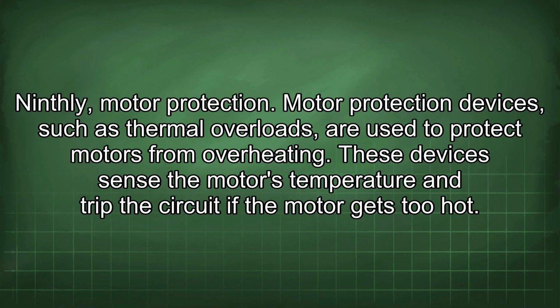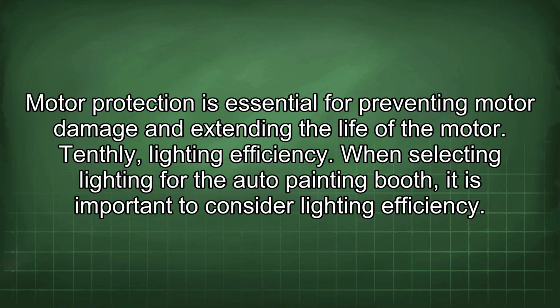Ninthly, motor protection. Motor protection devices, such as thermal overloads, are used to protect motors from overheating. These devices sense the motor's temperature and trip the circuit if the motor gets too hot. Motor protection is essential for preventing motor damage and extending the life of the motor.